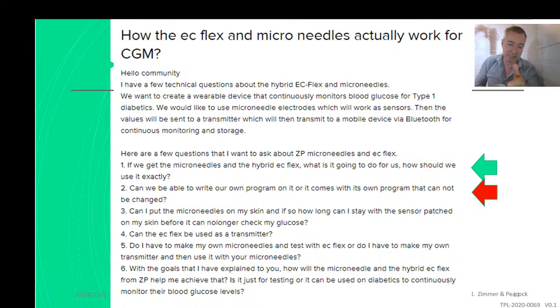you're building a glucose system. So this allows you to do your prototyping, your early development, but the glucose system that you want to develop has to be approved, obviously, at least in your own country. But then, if you want to sell it in the US, by the FDA, and if you want to sell it in Europe, then you have to get CE marked. So we provide these microneedles so that people can start doing prototyping and development. But I can't sit here and approve that you stick those into your skin. I will, but that's my choice as an individual. But I will not recommend or even encourage in any way that you do that. Otherwise, that would be saying that we're selling them as a medical product to be used on patients, and that's not what we're doing. We're providing them as tools so that engineers who are interested in things like AI and app development and want to develop technologies for diabetics can get a flying start on this.